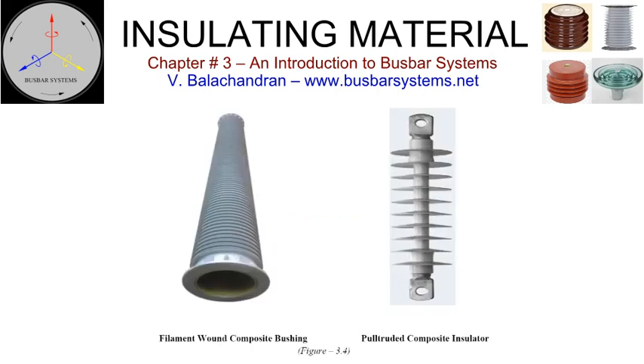The core can be a pultruded rod of glass epoxy as in the case of transmission lines, string insulators, or can be a filament wound cylinder as in the case of post insulators in switch yards. Housings of high-voltage oil-immersed current transformers and voltage transformers also use composite insulation. The filament wound cylinder diameter can be profiled from top to bottom for optimal design.